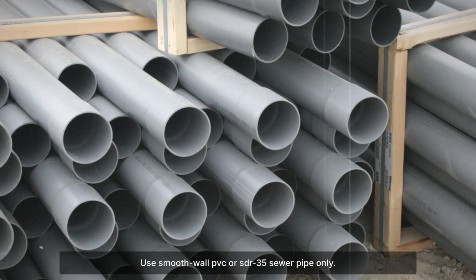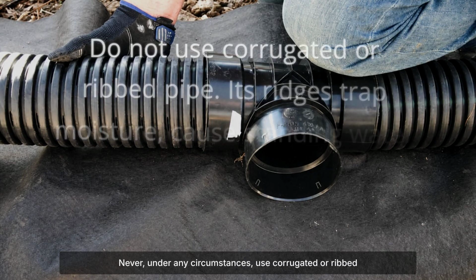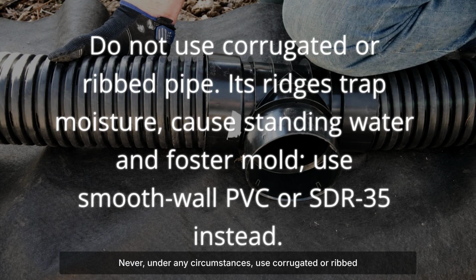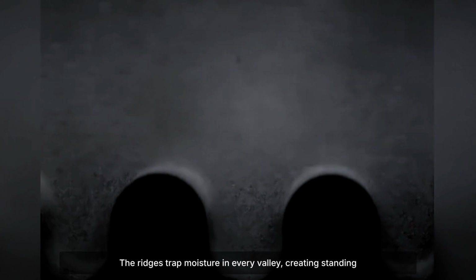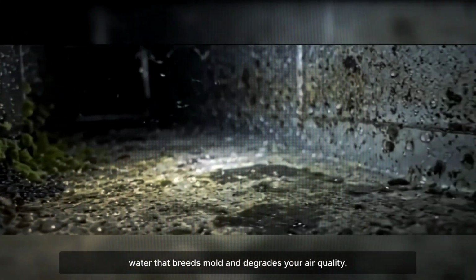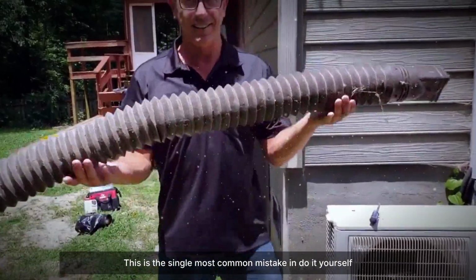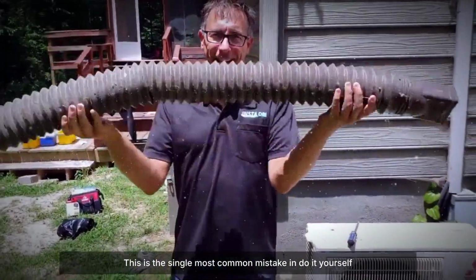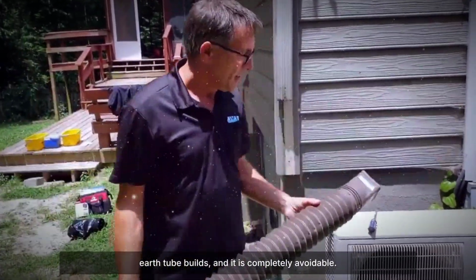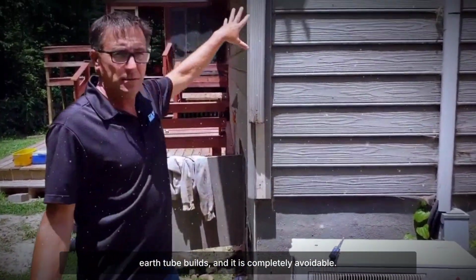Use smooth wall PVC or SDR35 sewer pipe only. Never, under any circumstances, use corrugated or ribbed pipe. The ridges trap moisture in every valley, creating standing water that breeds mold and degrades your air quality. This is the single most common mistake in do-it-yourself earth tube builds, and it is completely avoidable.